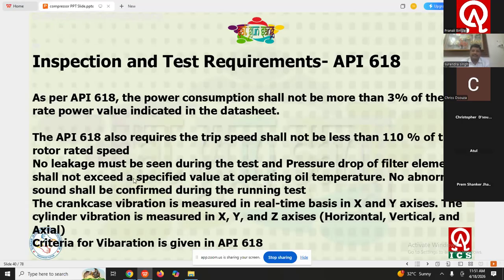No leakage must be seen. Another requirement defined in 618 is that no leakage must be seen during the test, and the pressure drop of the filter element shall not exceed the specified value. So we have to check the pressure drop of the filter element. No abnormal sound shall be confirmed during the running test. So if you hear any abnormal sound, you just note it down.